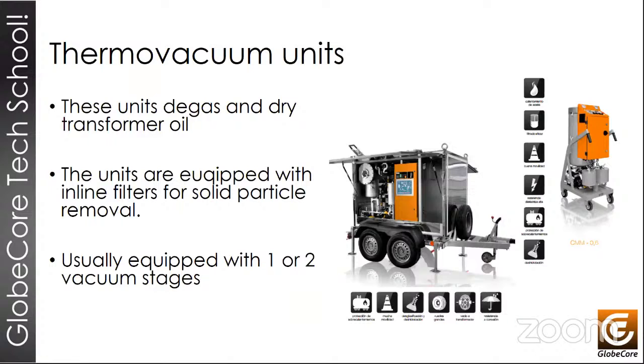There is a number of different thermal vacuum units. This is the equipment for degassing and for drying dielectric oil. It can do filtration and degassing, obviously. And this type of machine can have one vacuum stage or two vacuum stages. The two-stage equipment is usually the larger one. As you can see in this slide, the machine on the left has a double-stage vacuum system, and the little cart on the right has a one-stage vacuum system. But they basically perform the same function, the same purpose. So two-stage equipment is usually larger, obviously, and the Globecore has equipment with two-stage vacuum systems that has capacities anywhere from 1,000 liters per hour and up. Next slide, please.